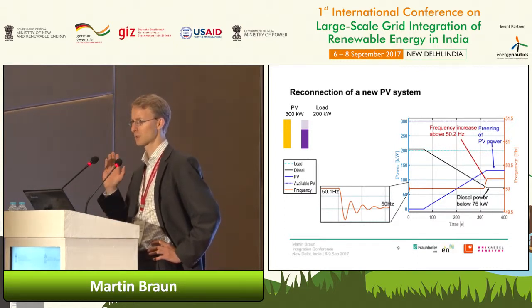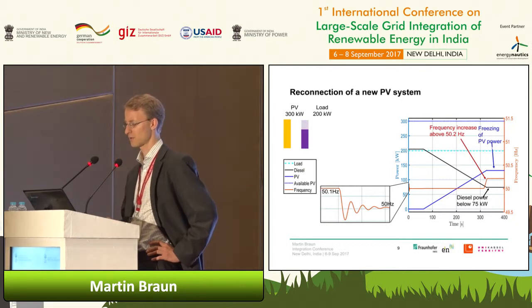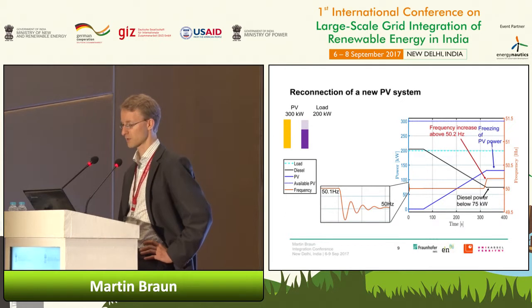So the frequency now is a signal that defines the sharing of the load between the diesel genset and the PV power, ensuring that not too much PV is feeding in, and that the diesel genset is not in underload operation. So this is working quite fine.